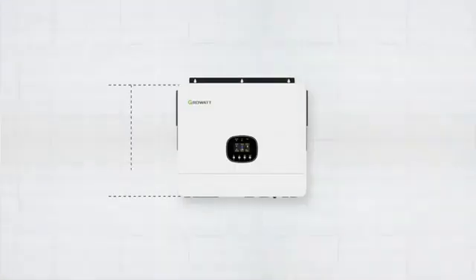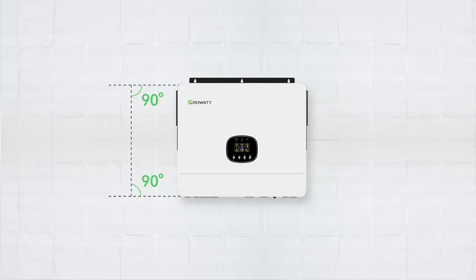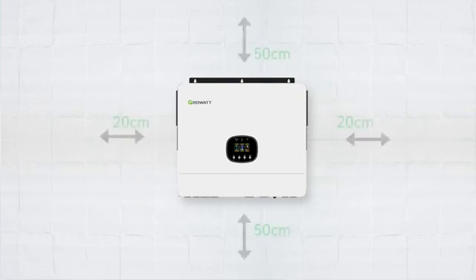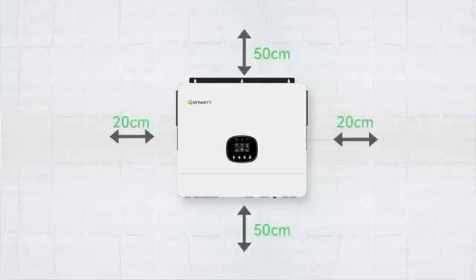The recommended installation position is vertically adhered to the wall. For proper air circulation to dissipate heat, allow clearance of approximately 20 cm to each side and approximately 50 cm above and below the unit.